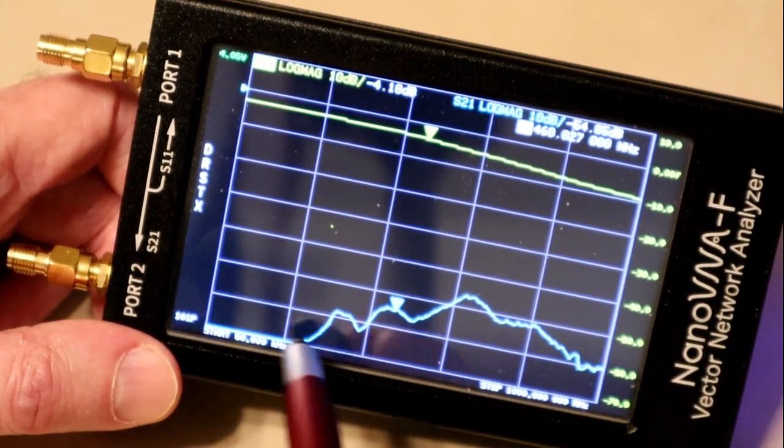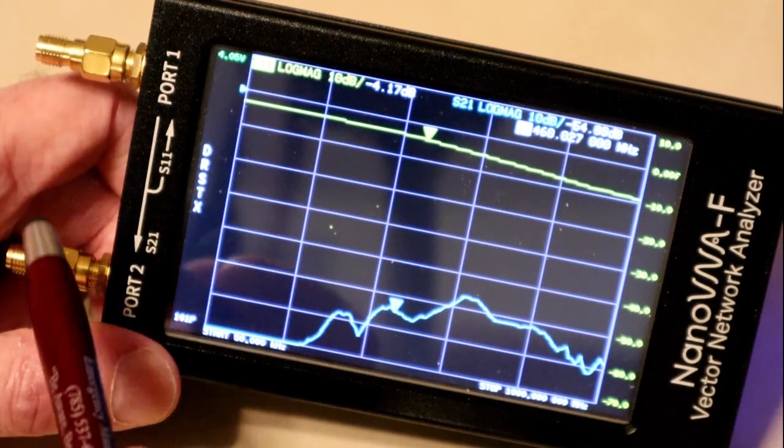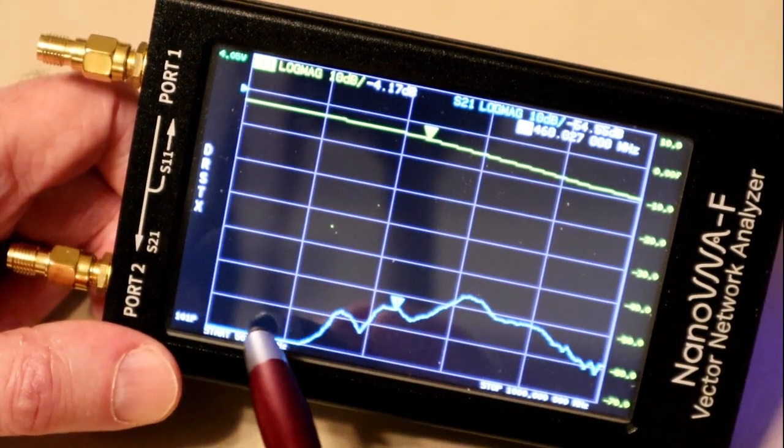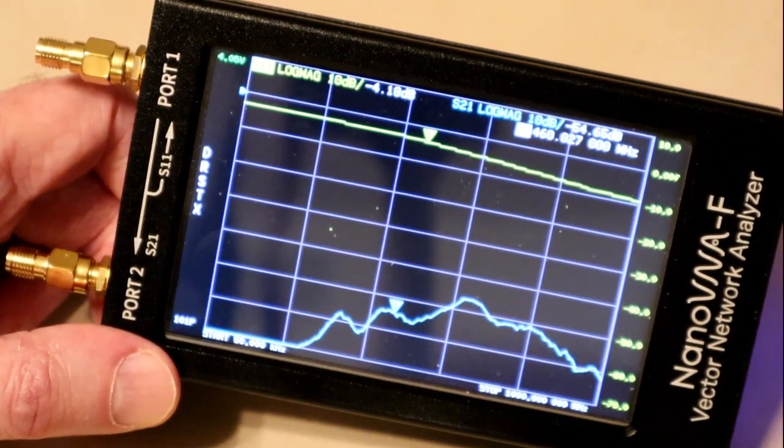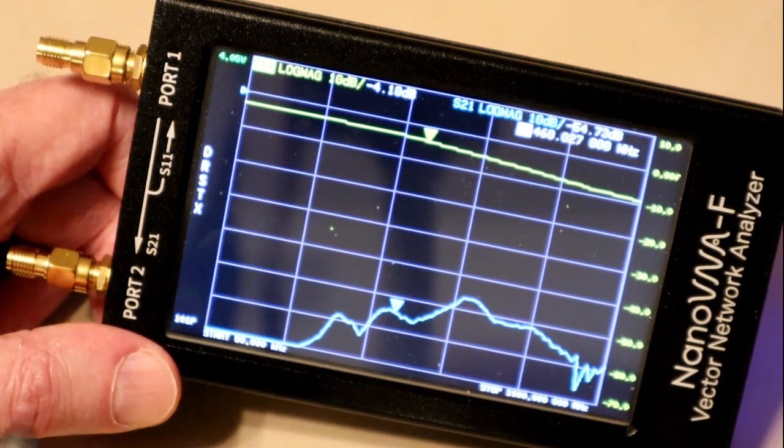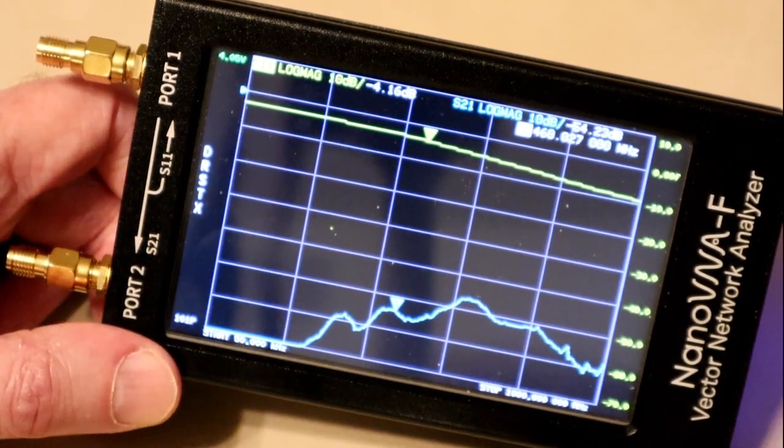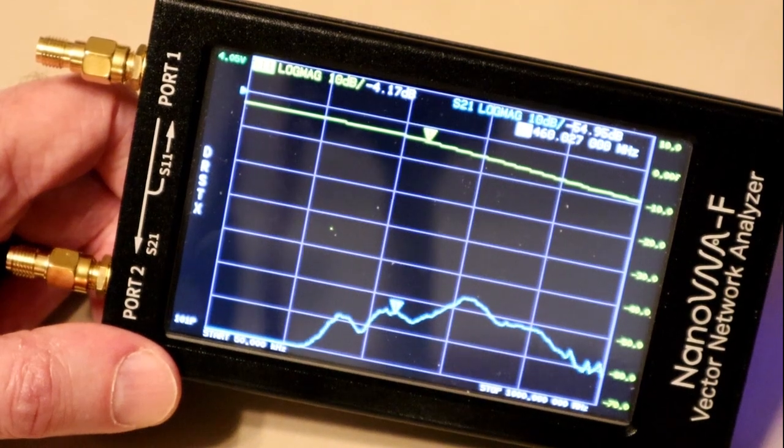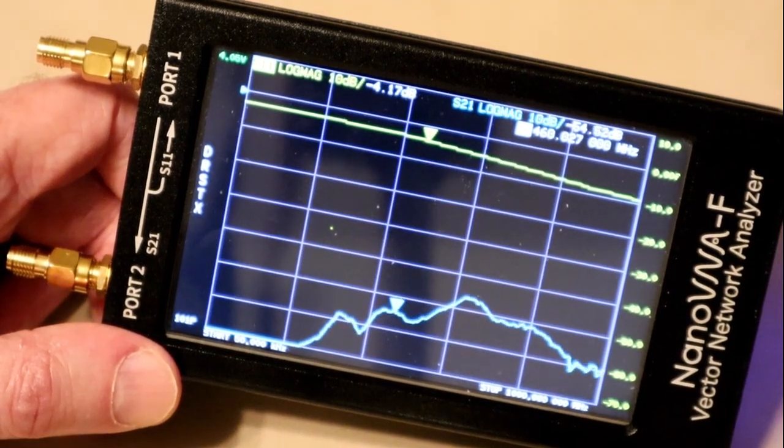S21 should be very low down here because port 1 is not connected to port 2, but it actually jumps up, and that's due to limited isolation inside the instrument from port 1 to port 2. And that can be corrected for, to a certain extent, if you have the right test setup.